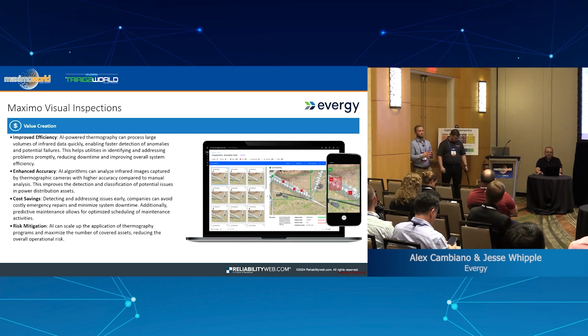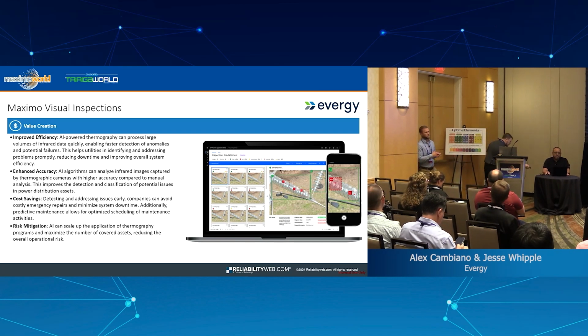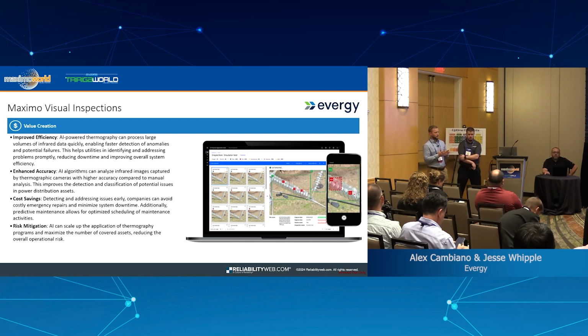What we're excited about with this - and we're still in a development phase with PwC on this right now, for the record - is it takes, as we talked about, there's a guy or a gal going out there doing these scans, and it takes some of the subjectivity out of it, some of the human performance issues you might run into. The way we currently do it, the craft person goes out there, sees something, and there's an expected range. A lot of times we're fortunate enough that we're dealing with three-phase power, so we're looking for one of the three that doesn't look right.